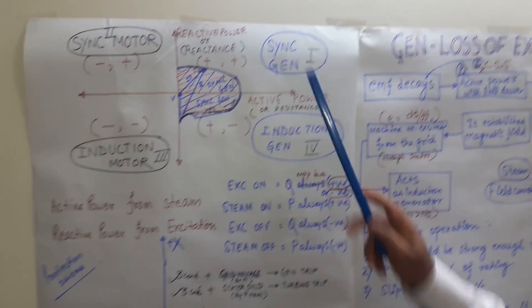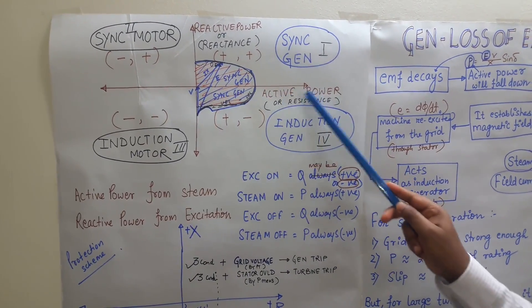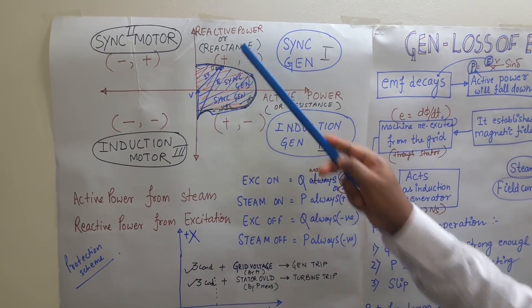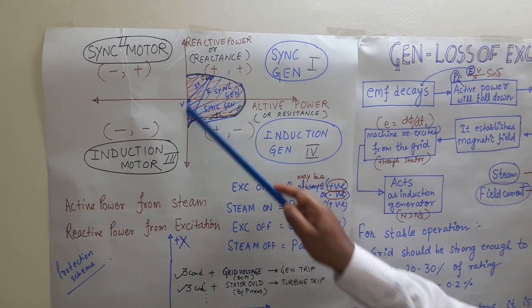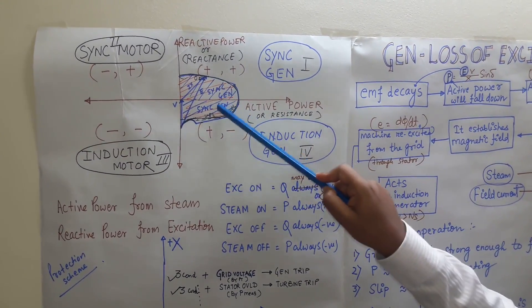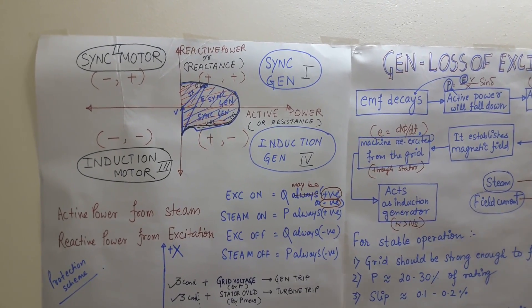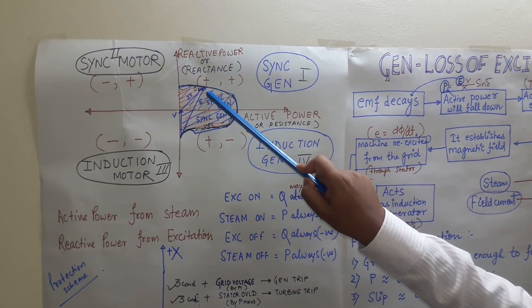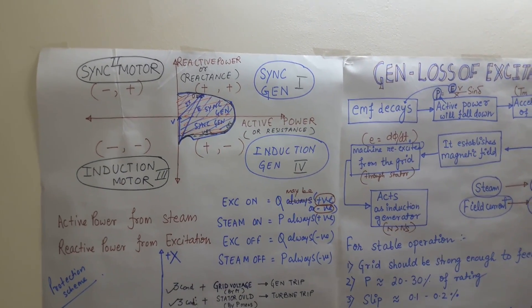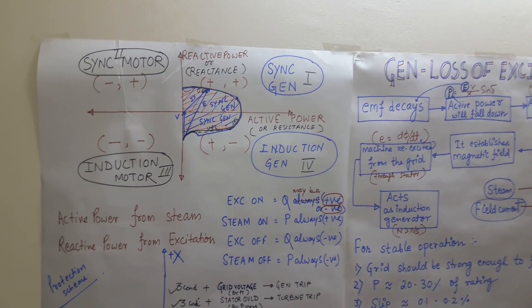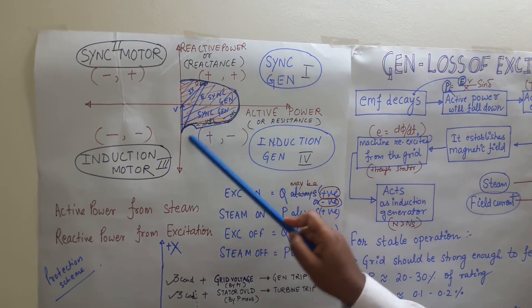Look at this picture. The X axis stands for active power and the Y axis stands for reactive power. This is the capability curve of the generator. If the generator is operating within this zone, the generator is in healthy condition. If the operating point is going out of this zone, the generator is operating at abnormal condition.